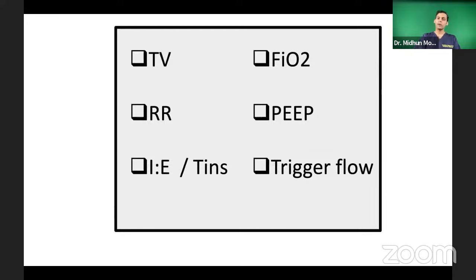Now, when you set the respiratory rate, suppose the rate has been set as 20, so every 3 seconds one breath will be delivered, right? Now, this 3 seconds should include both inspiration as well as expiration. So in the machine, you have the option of setting something called the IE ratio, inspiration to expiration ratio. Usually we start it as 1:2 because expiration usually requires double the amount of time.